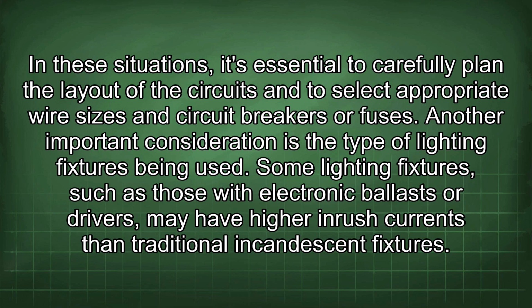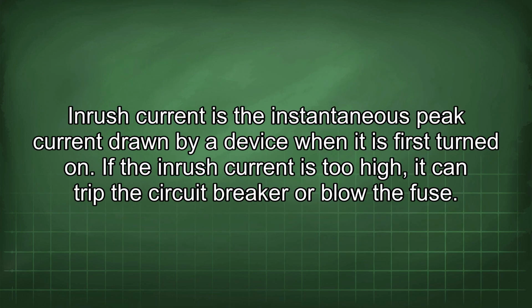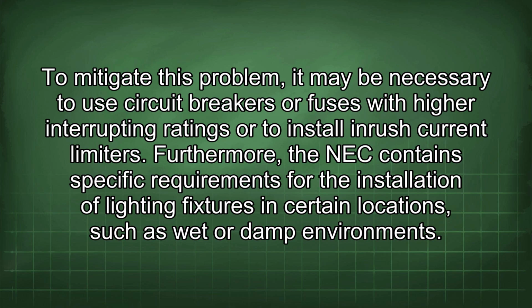In these situations, it's essential to carefully plan the layout of the circuits and to select appropriate wire sizes and circuit breakers or fuses. Another important consideration is the type of lighting fixtures being used. Some lighting fixtures, such as those with electronic ballasts or drivers, may have higher inrush currents than traditional incandescent fixtures. Inrush current is the instantaneous peak current drawn by a device when it is first turned on. If the inrush current is too high, it can trip the circuit breaker or blow the fuse. To mitigate this problem, it may be necessary to use circuit breakers or fuses with higher interrupting ratings or to install inrush current limiters.